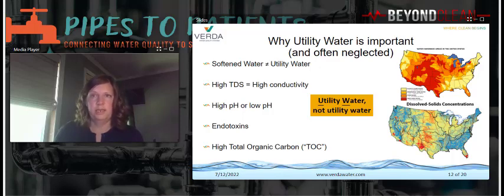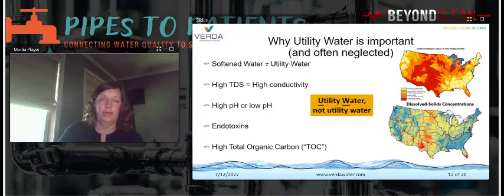Since water softening is an ion exchange process, you're replacing calcium and magnesium ions with sodium or potassium ions. The number of dissolved solids in the water hasn't changed. So the total dissolved solids and the water conductivity will stay the same. It's not uncommon for some regions in the country to have municipal city water that's simply too high of conductivity, even for the USP utility water.